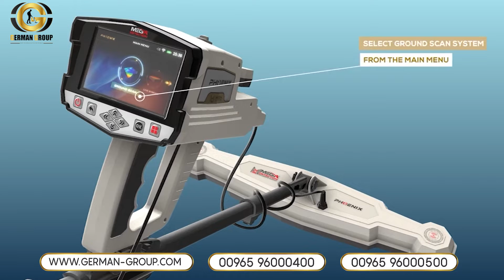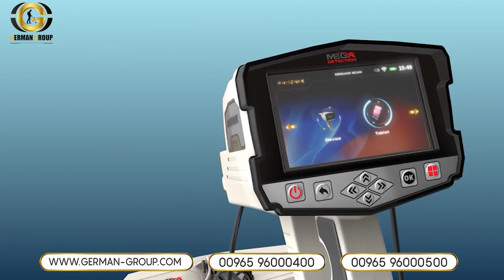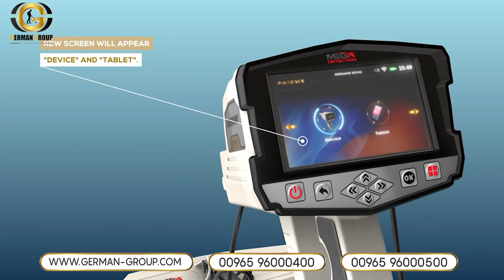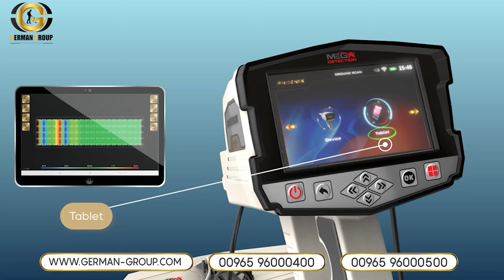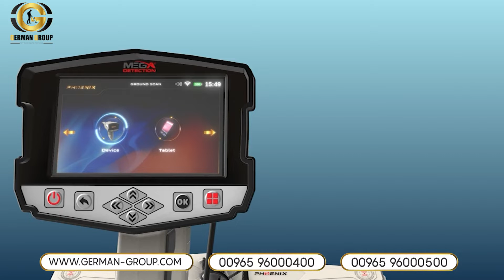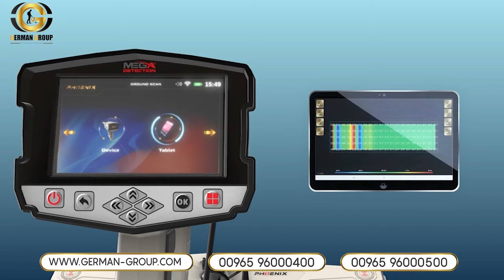System selection. To start using the ground scan system, select it from the main menu. After selecting the ground scan system from the main menu, a new screen will appear to select the device on which the results will be displayed. There are two options: device and tablet. Selecting device in this list means that the user can see results directly on the device screen. Selecting tablet in this list means that the user can see the results on the tablet screen that came with the device, that includes multi-visual analyzer application to display the results visually.